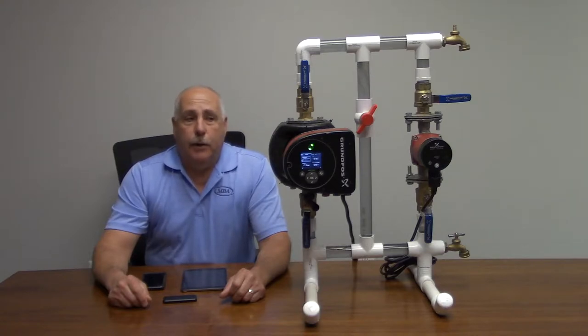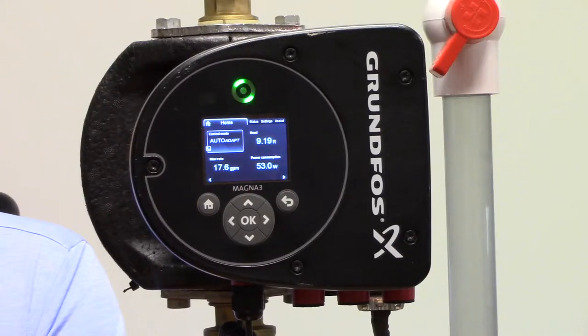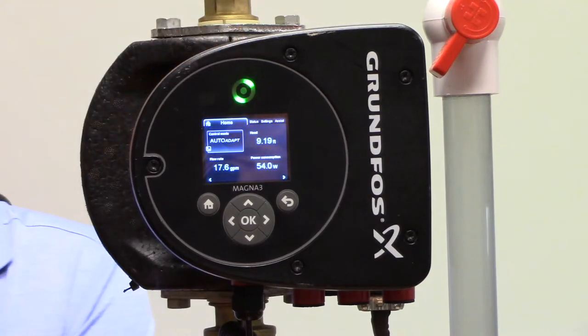First thing that we'd like to talk about is something called the eye. If it's rotating, the pump is running. If it's steady, the pump is waiting to run but it's physically on. There are three different colors: green, everything is running fine; yellow indicates a warning; and red indicates an alarm.